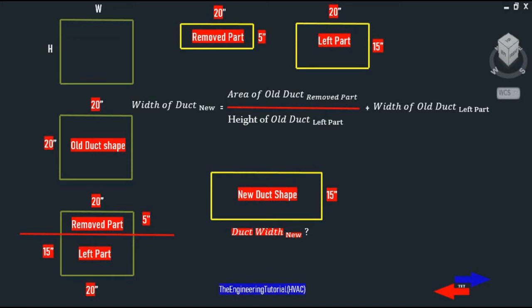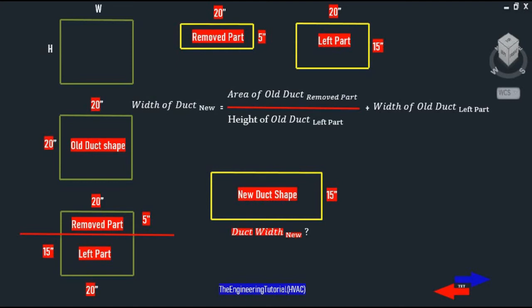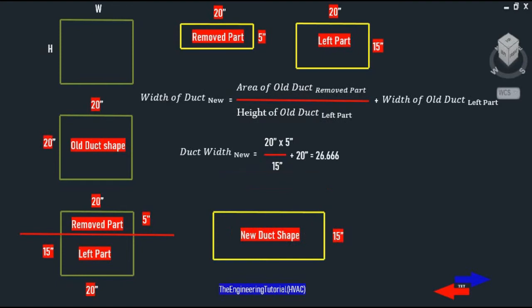First of all, we need to determine how many square inches of duct we want to remove from the existing shape. We have an existing duct of 20 by 20 inches. If we remove 5 inches from the height, then 5 times 20 equals 100 square inches to be removed. To find the width of the new duct shape, we use this formula: the width of new duct equals the area of the removed part divided by the height of the remaining part, plus the width of the old remaining part.